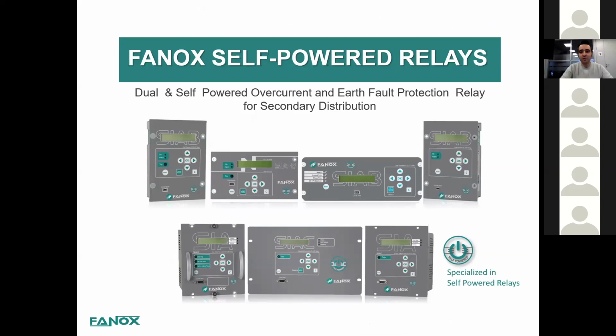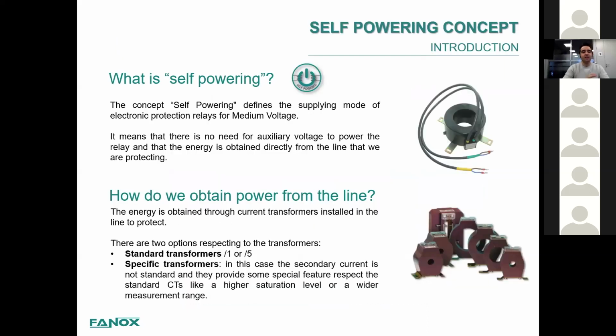Just a reminder, I'm pretty sure most of you have attended our previous webinar about self-power relays, but in case you didn't, or just to remember, what is a self-power relay? Traditional relays need an auxiliary power to be powered. It means that in some locations where this kind of power cannot be assured, or even in events that make the UPS system or the auxiliary system go down, these relays will be useless. For this reason, the self-power relay doesn't need an auxiliary voltage because it takes the energy directly from the currents that are connected to the lines. It means that as soon as there is any current flowing on the system, the relay is going to be powered up and all the functions will be working properly.